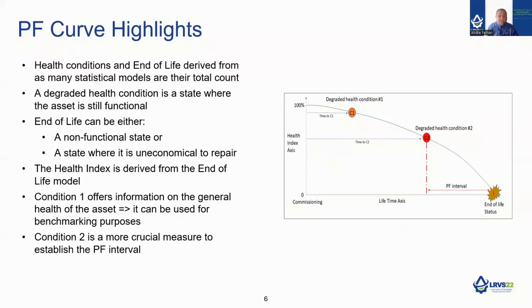To get F, C1, or C2, as shown on the curve here, we use reliability engineering principles defined earlier, where each of the three values are characterized by a unique statistical distribution. In other words, they each have a unique distribution because they are statistically different. For example, C1 is obtained from infrared inspection, C2 from a vibration inspection, and F from functional failure records, if you want.